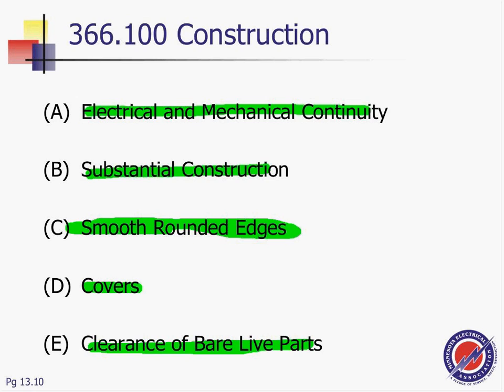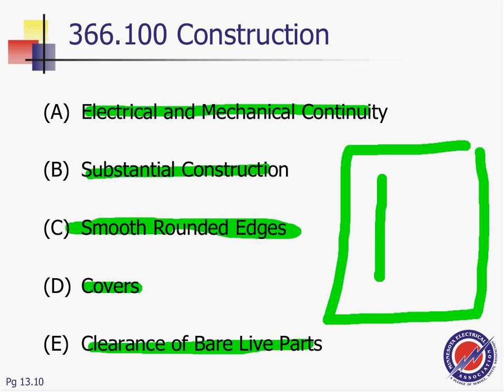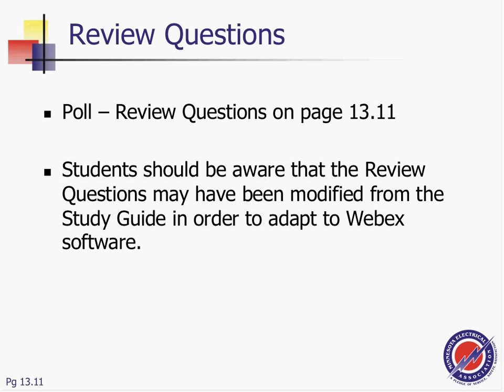If inside your panel, remember we have bars: phase A, phase B, phase C, and then neutral. You have to maintain the clearance between these uninsulated bare live parts. I'm going to leave that one.